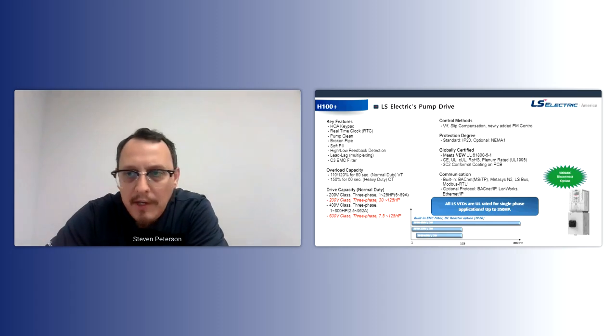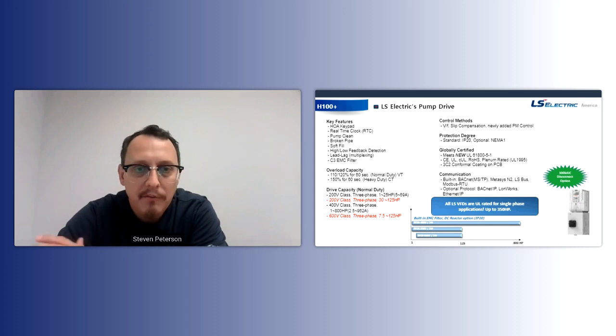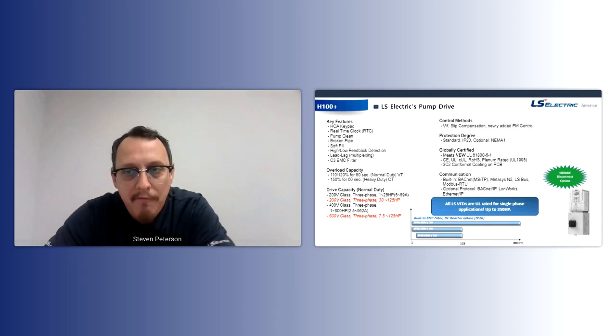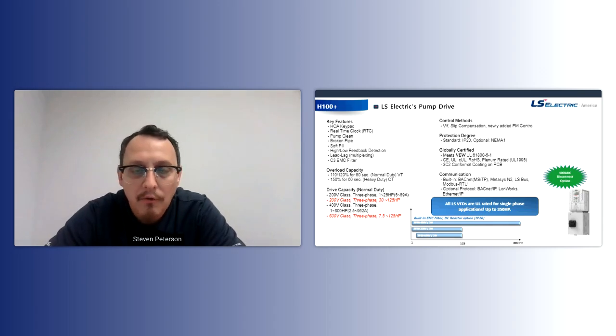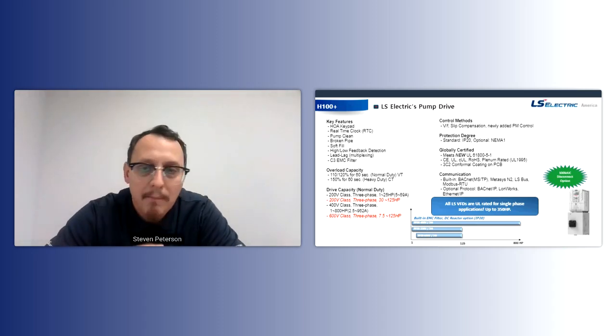Additionally, we have all the standard control methods you may run into with any existing units you may be utilizing. We default to a V/F control, a V/F frequency control, so the output voltage going to the motor is determined by a predefined pattern of voltage over frequency. We do have a slip compensation. We also have a newly added V/F control with permanent magnet control. Most of the time people are using induction motors, but if you happen to have a permanent magnet motor, we could run that off of the H100 Plus as well. That's a simple parameter that you enable.